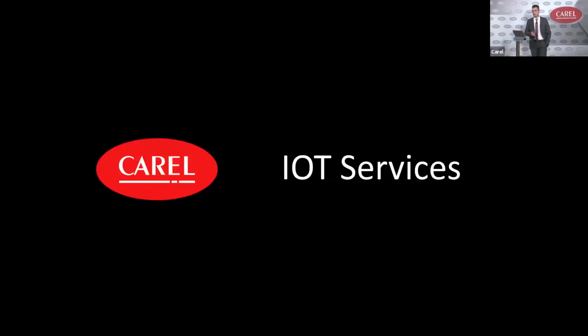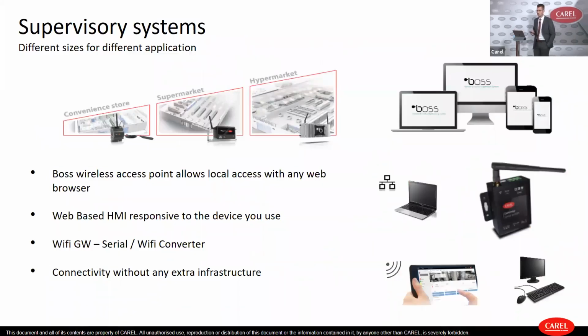And this is bringing us to speak about CAREL IoT services. Before speaking about the services, I would like to give you a quick overview of our supervisory system. So a supervisory system is a device that is collecting and showing, and makes you able to check the units, the cabinets, change parameters, and optimize the working conditions of these devices.